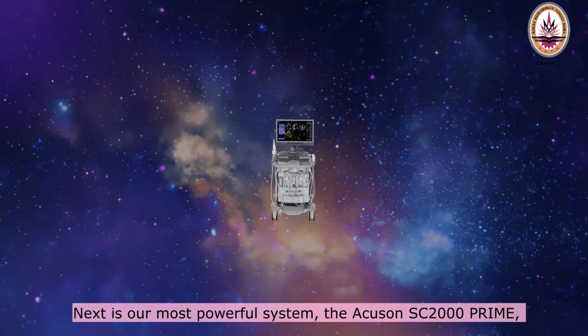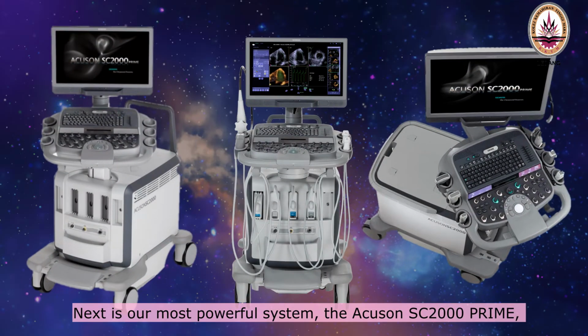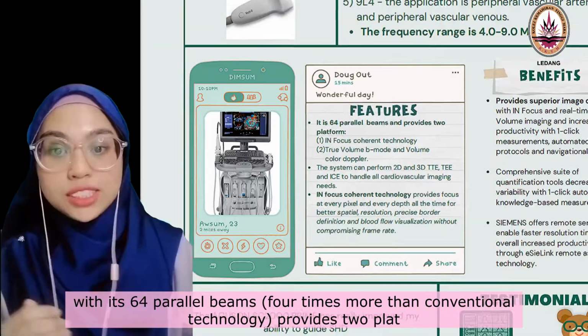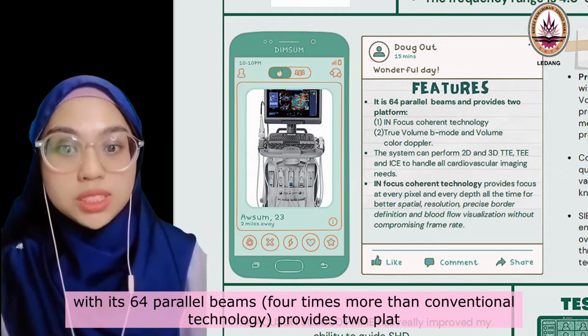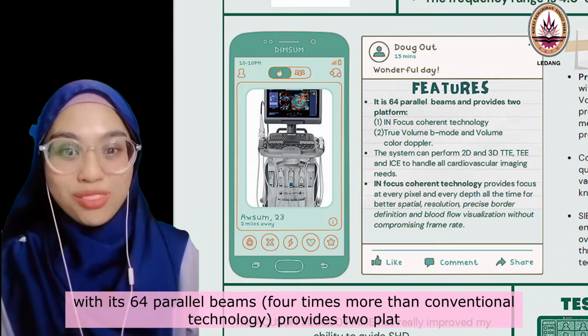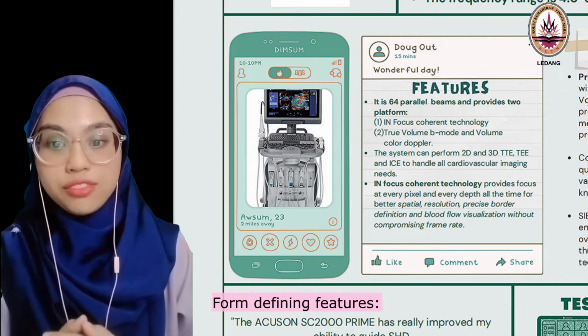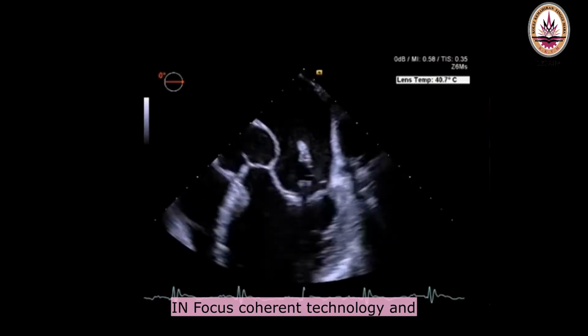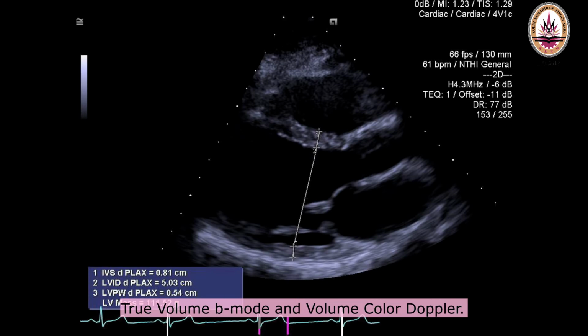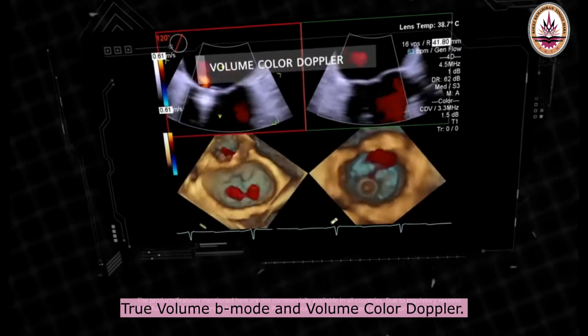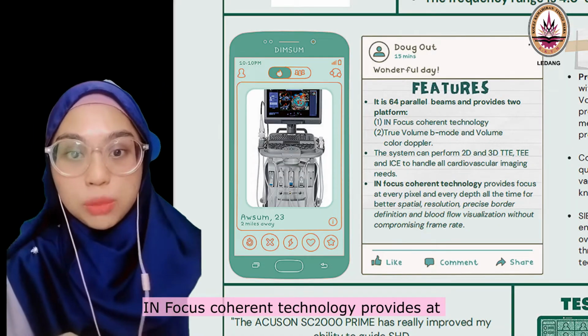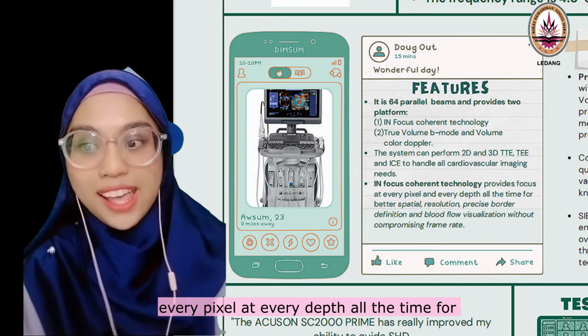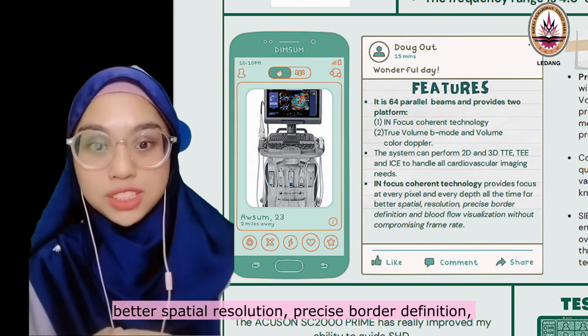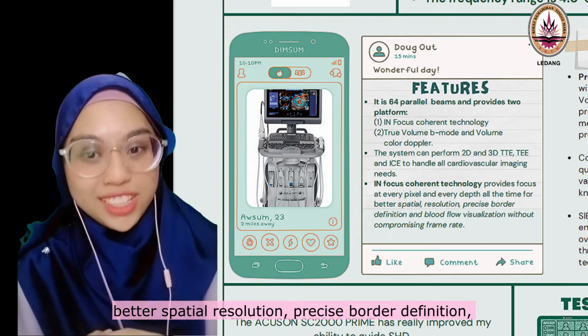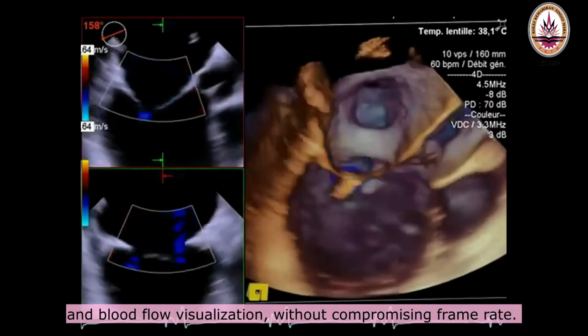Next is our most powerful system, the Acuson SC2000 Prime, with 64 parallel beams, 4 times more than conventional technology provides. Defining features include IN Focus coherent technology true volume b-mode and volume color Doppler. IN Focus coherent technology provides, at every pixel and at every depth, all the time, for better spatial resolution, precise border definition, and blood flow visualization without compromising frame rate.